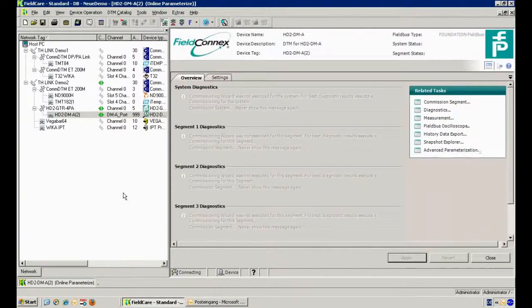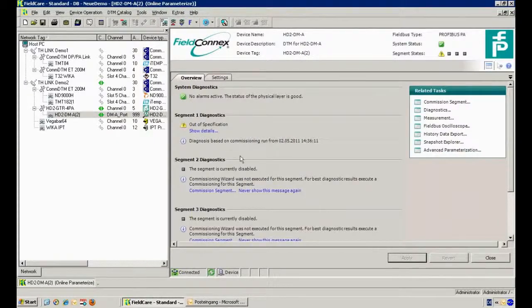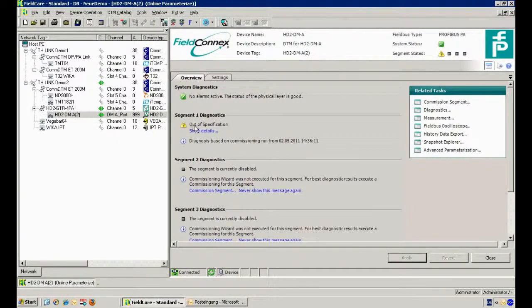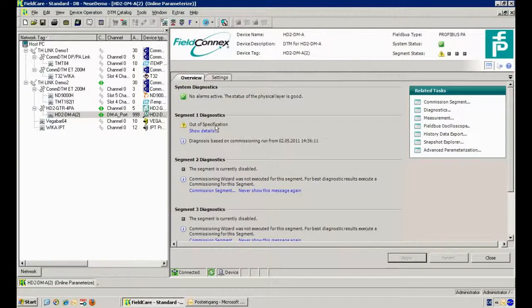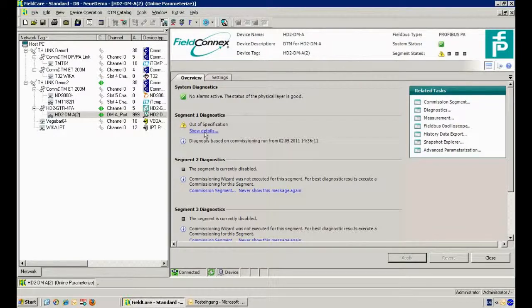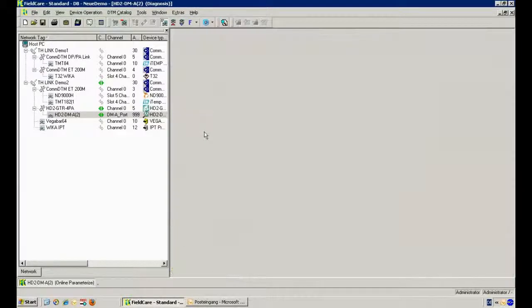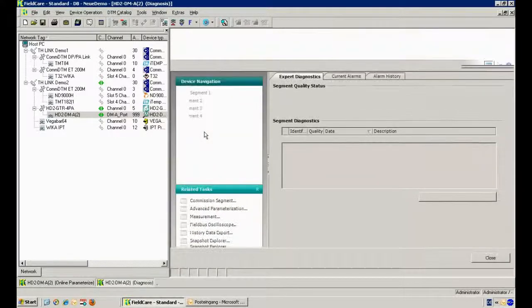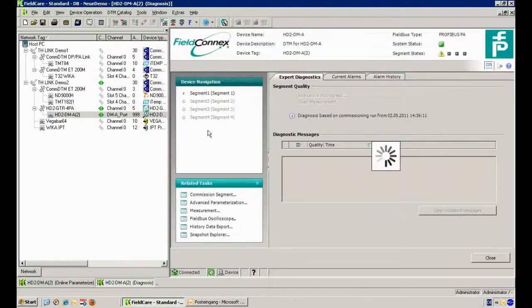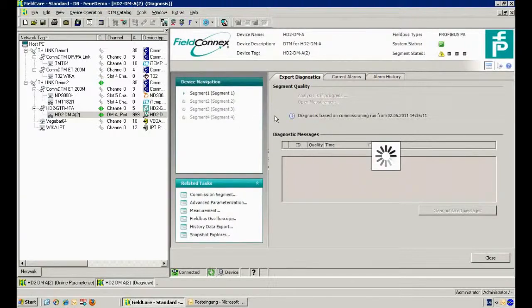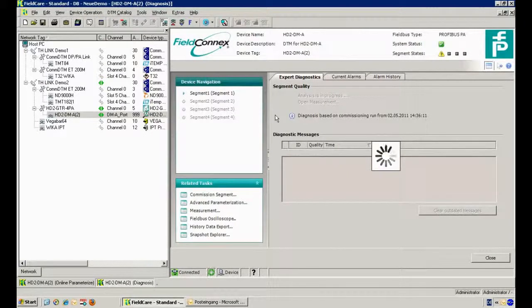Via online parameterization we open the DTM, the diagnostic DTM from P&F, and see all the details. The message here is segment 1 diagnostics and the segment is out of specification. We can go deeper showing details and then the DTM will provide the detailed information about the root causes for the problems.